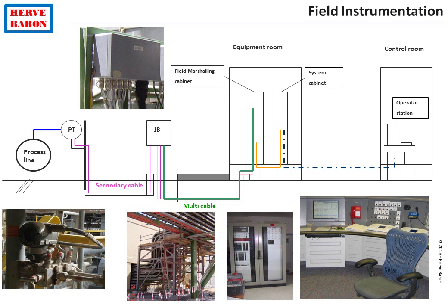This synoptic shows all instrumentation and automation hardware, including instruments connected to the process lines, secondary cable connections of instruments to junction boxes, the connection of junction boxes by multi-core cable to the marshalling cabinet in the instrumentation equipment room, and the fiber optic connection from the instrumentation equipment rooms to the control room.